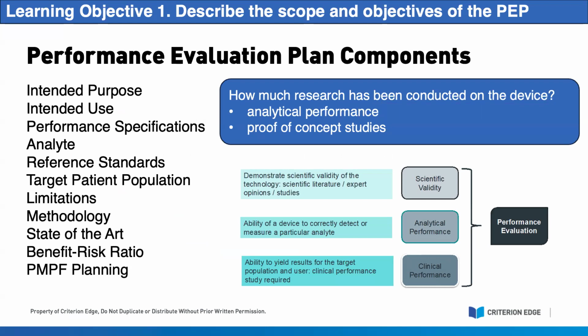You'll also want to describe the analyte and or whatever biomarker that is being measured by your IVD, and any related reference standards or ways of ensuring traceability for that particular biomarker. You also need to be very clear in the way that you identify your specific target patient groups, along with your indications and any limitations or contraindications. It's also important to take into account things like the global safety and performance requirements that your PE will support, as well as providing details on the methodology, including things like statistical tools that you're going to use to assess the analytical and clinical performance of your IVD.